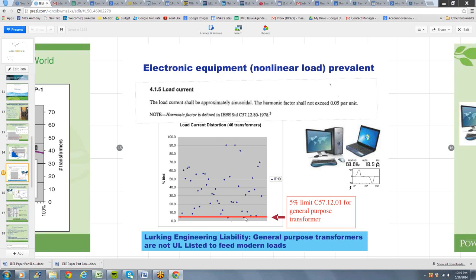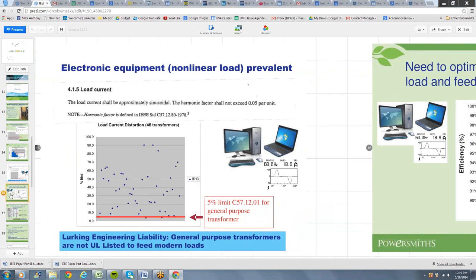So what it means is a general purpose transformer is definitely not approved for that purpose. From a new construction perspective, or retrofitting a transformer, you can't retrofit a general purpose transformer into that same space. You've got to recognize that the load profile is different, and as a function of that, put in a transformer that is K-rated for that kind of load profile. So now we've got a light loaded transformer and the reality that we're feeding electronic equipment, right?